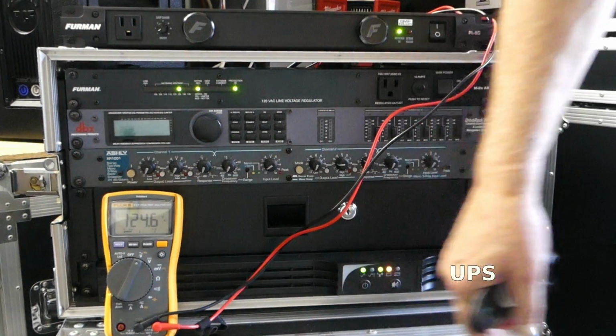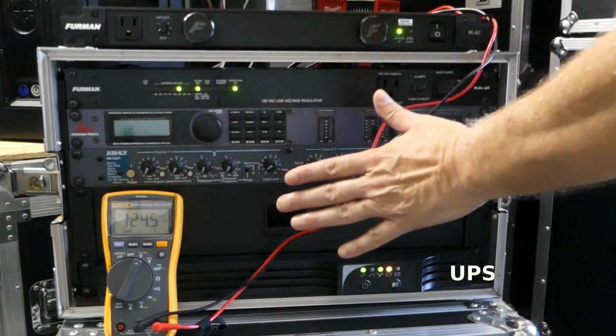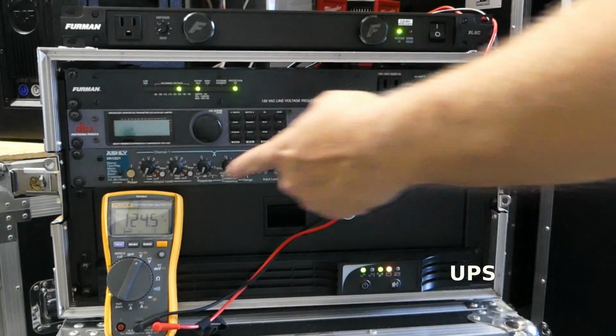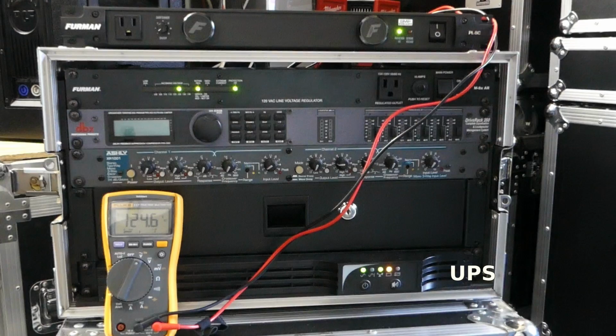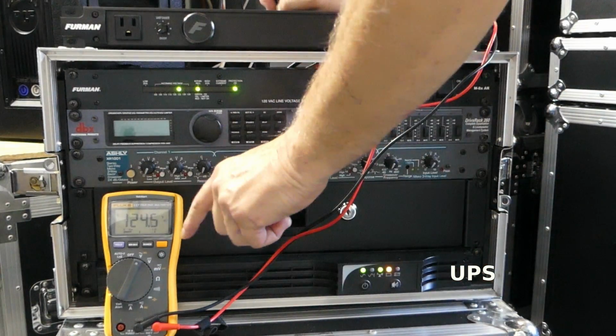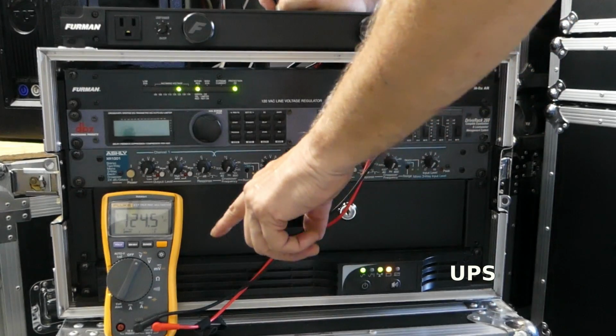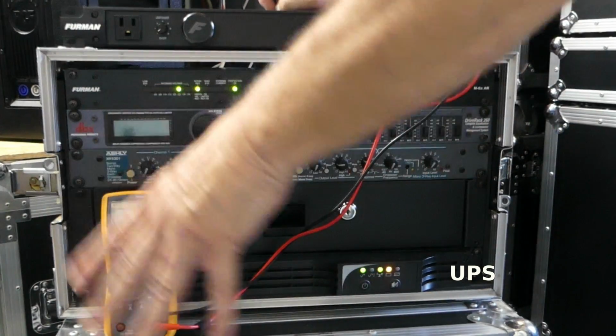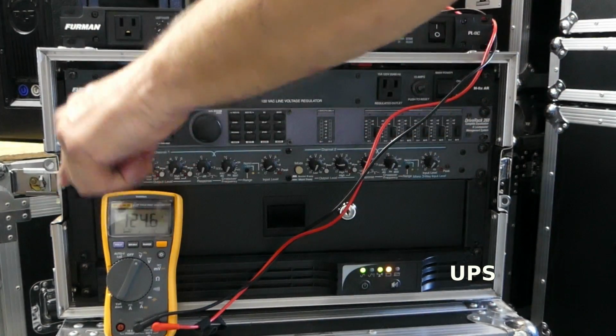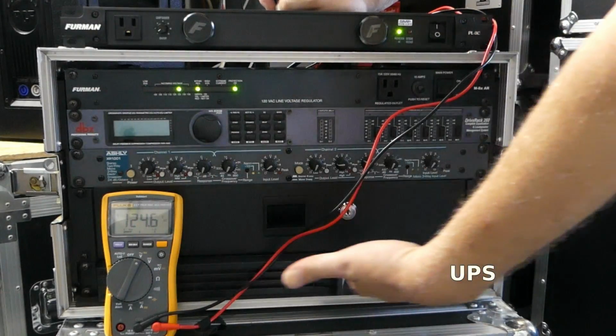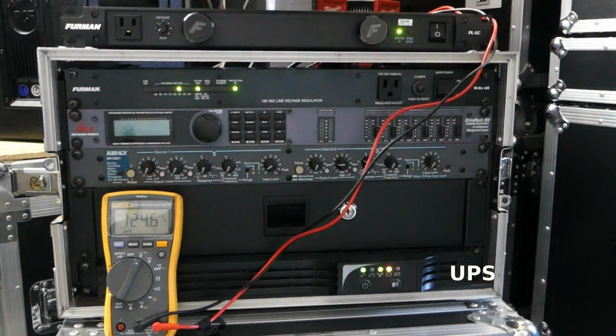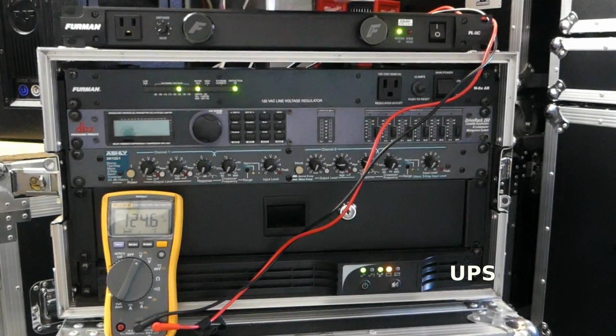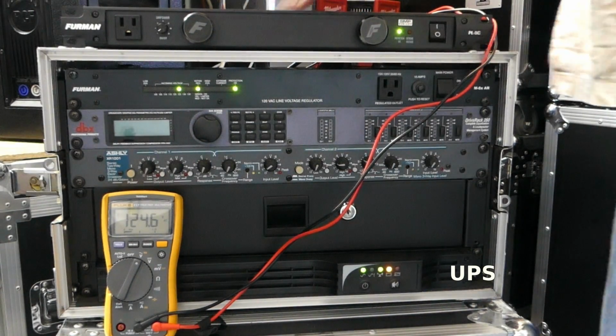On the UPS here, it is sending out on the outlets in the back 125 volts. Now the difference here can be when the UPS loses power. So the only thing right now the UPS is doing is taking the power from the wall, the utility power, and sending out the same amount of power out the outlets. It's doing exactly what a regular PDU does.